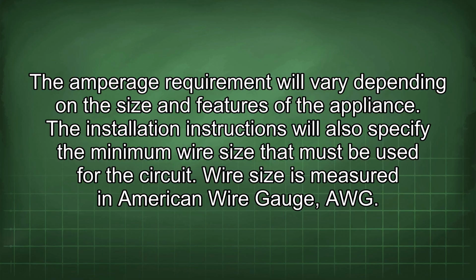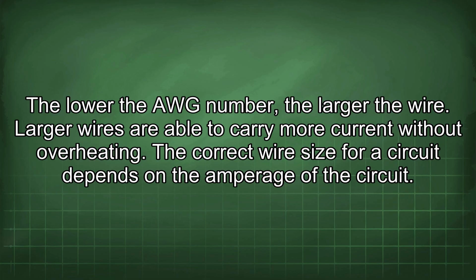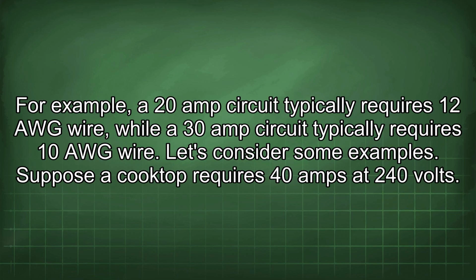Wire size is measured in American wire gauge (AWG). The lower the AWG number, the larger the wire. Larger wires are able to carry more current without overheating. The correct wire size for a circuit depends on the amperage of the circuit. For example, a 20 amp circuit typically requires 12 AWG wire, while a 30 amp circuit typically requires 10 AWG wire. Let's consider some examples.